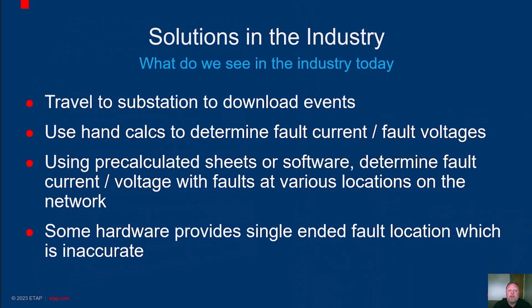In the current industry landscape, users often face challenges in fault location and analysis, including the need to travel to substations to download events, relying on hand calculations to determine fault currents and voltages, and using pre-calculated sheets or software to estimate fault parameters at various locations on the network. It's more of a guess and check and lookup tables. Additionally, some hardware solutions provide single-ended fault location, which may result in inaccurate or unreliable fault location results, further complicating the process. These challenges can result in extended downtime, reduced system performance, and financial losses. To overcome these issues, there is a growing need for advanced fault location solutions that leverage real-time data and sophisticated algorithms to improve fault location accuracy, reduce downtime, and enhance system performance.